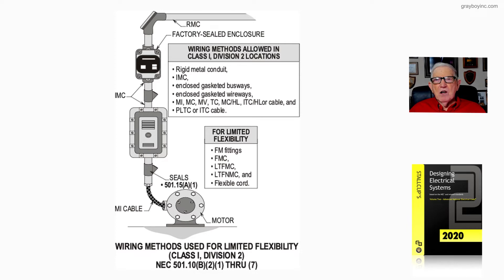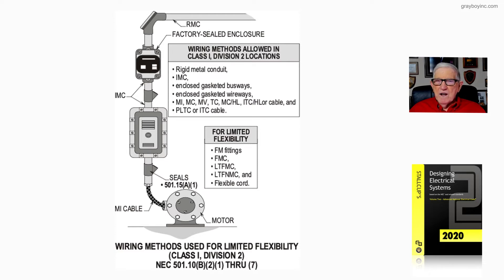At the very top of the illustration, we have rigid metal conduit, a 90-degree type L, coming into a factory sealed enclosure — so no seal is required there.